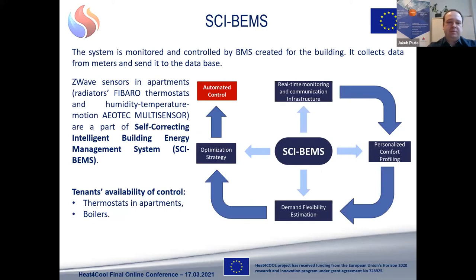In the building, we implemented a self-correcting intelligent building energy management system. The system mainly consists of Z-Wave equipment, like the Fibaro thermostats on the radiators and multi-sensors, which provide information about inside temperatures in apartments, motion, and relative humidity. Together with our monitoring platform, we are able to control the thermostats, the heat pump, the circulation pumps in the building, and the photovoltaic installation and charging of the heat batteries. Also, tenants in the apartments have some possibility of control of their systems.